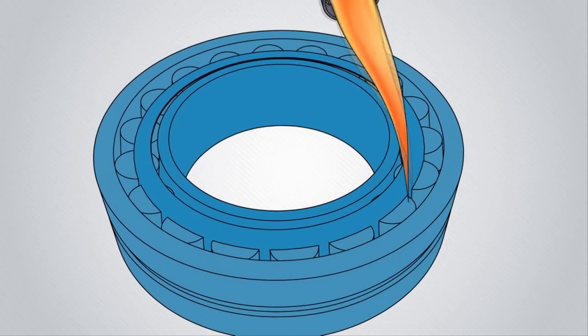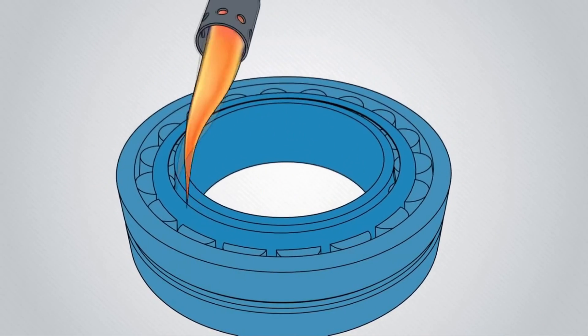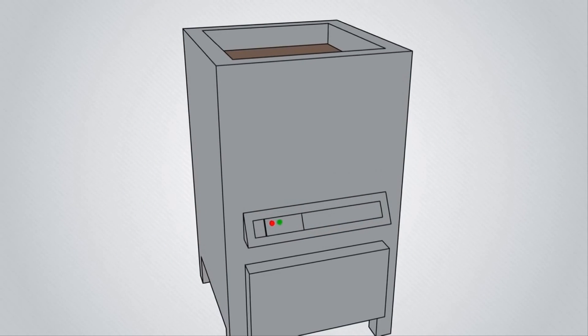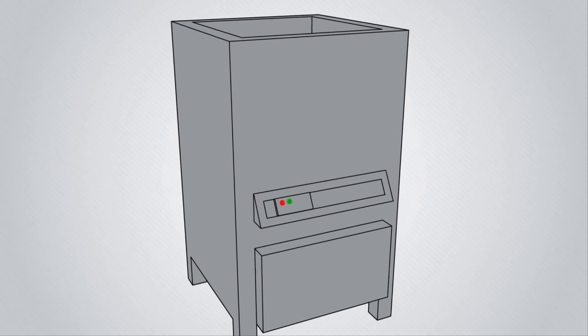Direct flame should never be used as the bearing can be damaged. Oil baths were once popular but can be slow, dirty, and present significant handling hazards.